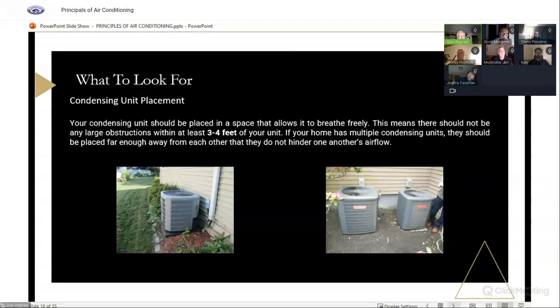If you look at the unit on the left, that whole back of that unit is a piece of sheet metal, so it can go closer to the house because the coil is not exposed back there. The coil is on the front, left, and right, and that has proper clearance provided those shrubs are away from the unit far enough. Right. These two units on the left and the right are too close to each other. I don't think that's 3 to 4 feet. Right, but if the system's working and people are being cooled properly and they don't have any problems, the HVAC guy is not going to come out when he's servicing it and say they should be moved. They're going to stay right where they are.